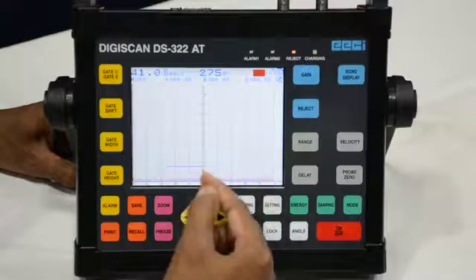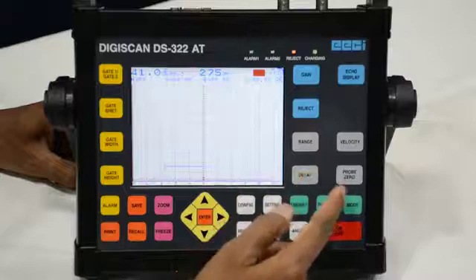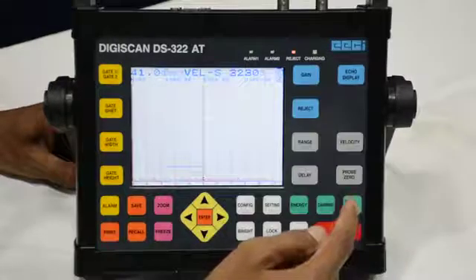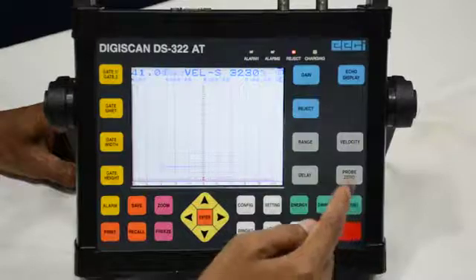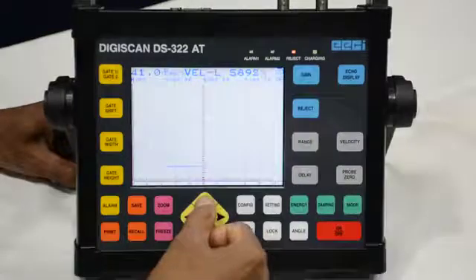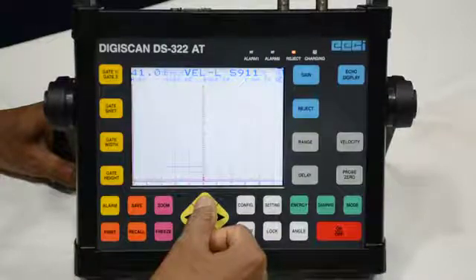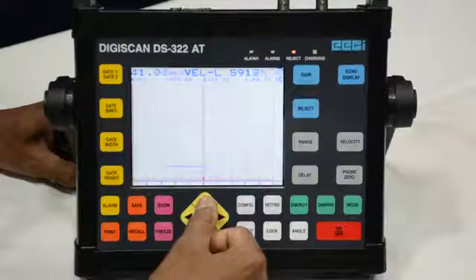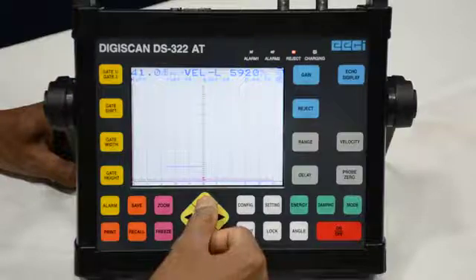This one is the velocity button. If our probe is a normal 0 degree probe, the velocity should be 5920. If it is not 5920, we have to increase it and make it 5920. If we are using an angle probe other than 0 degree, we have to set the velocity to 3230. As an example here, we have taken a normal 0 degree probe so we will make the velocity 5920.